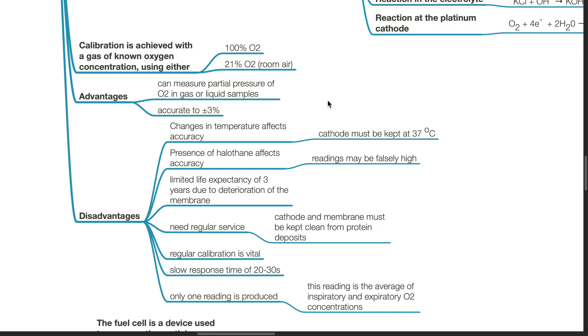Further disadvantages: it needs regular service, and the cathode and membrane must be kept clean from protein deposits. Regular calibration is vital. It has a slow response time of 20 to 30 seconds. Only one reading is produced, which is the average of the inspiratory and expiratory oxygen concentrations.